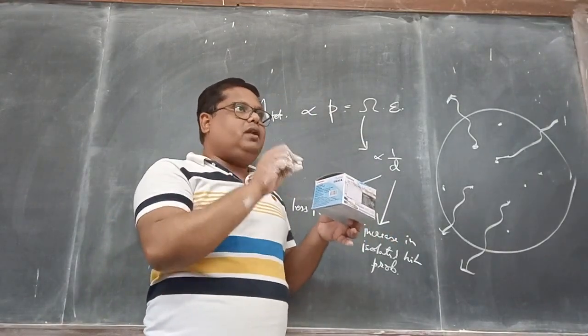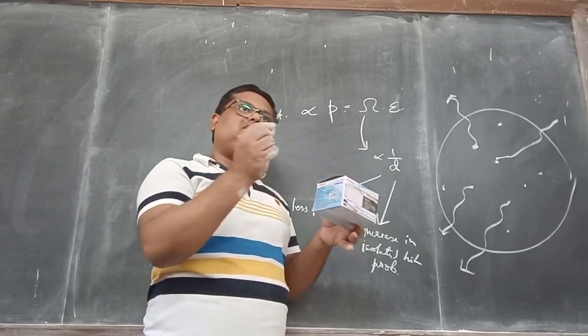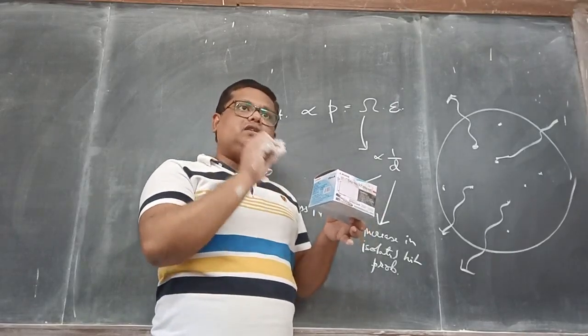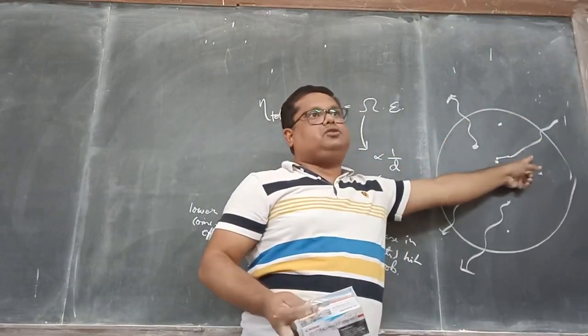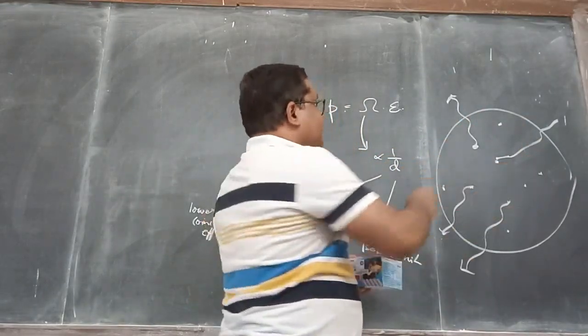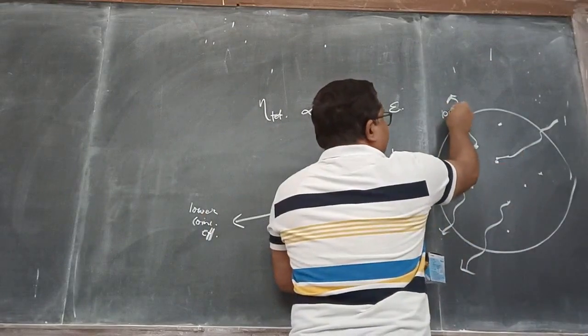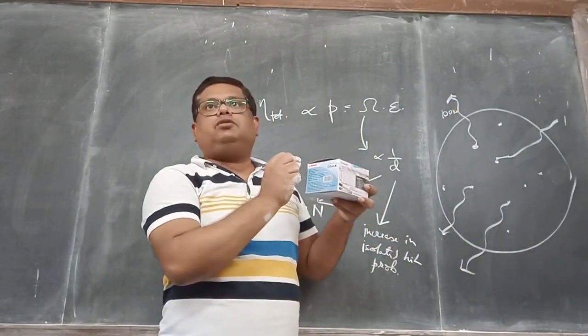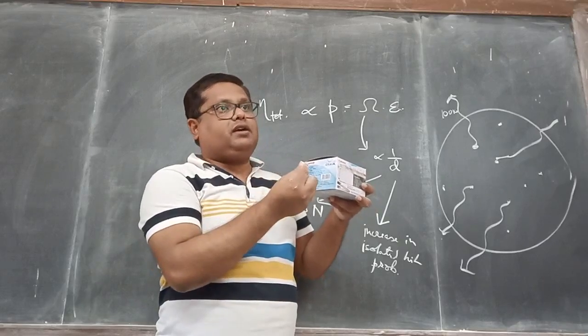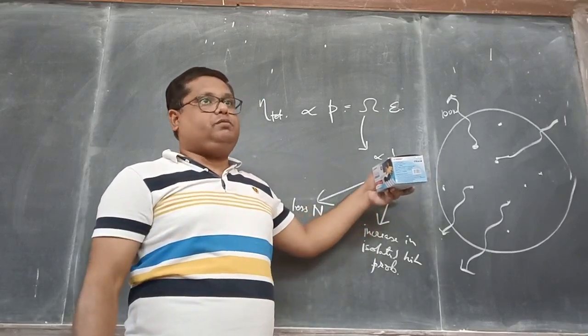So the detector will just give a signal equal to the sum of the energy deposited by these two counts. If each of the gamma rays has 100 keV, then the detector will show you a signal corresponding to 200 keV. Now this is isolated hit probability.